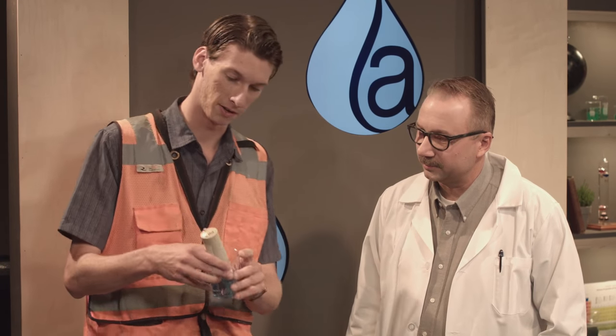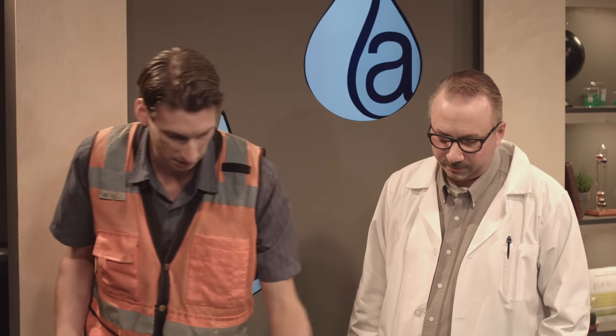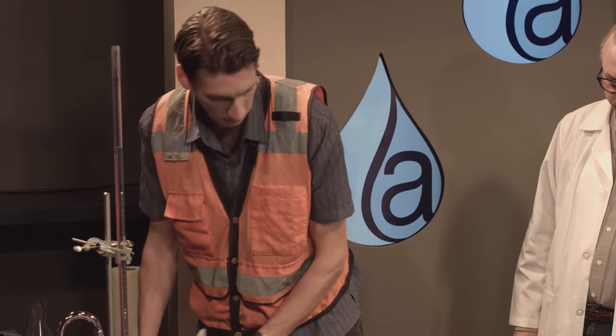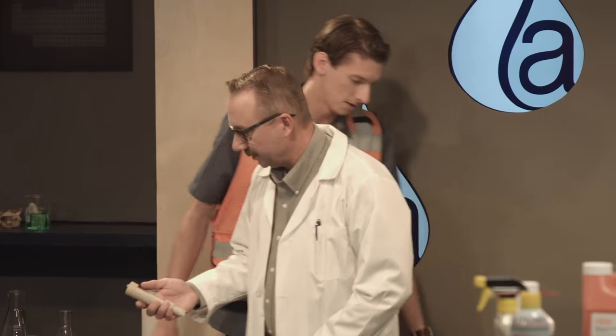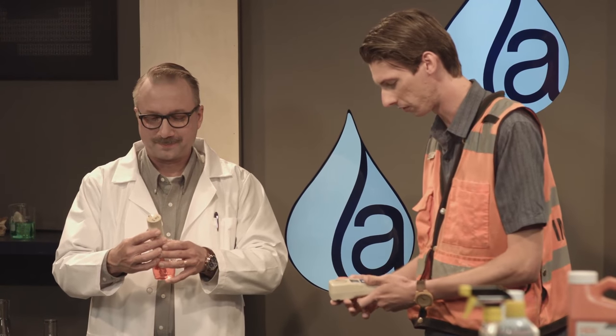Write it in a log — it's a permanent requirement that you keep records of your calibration logs, time and day. These turbidity meters — I've seen other similar ones, but we like the Oakton meters. They're all waterproof as well. The biggest thing to keep in mind is that turbidity measures the cloudiness of water, so you don't want to jostle it around because that agitates the material and could give a false reading.